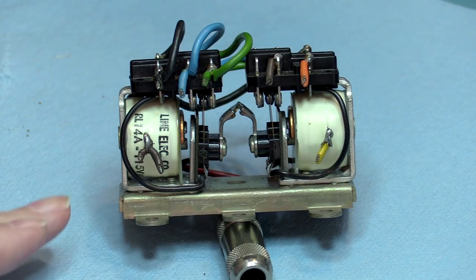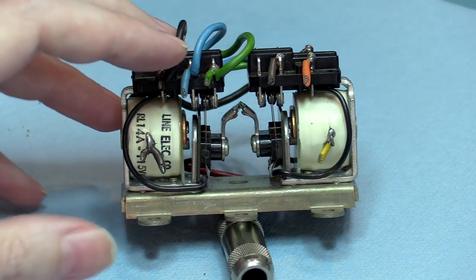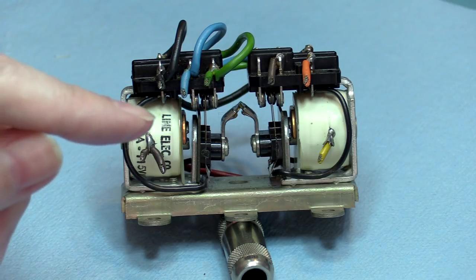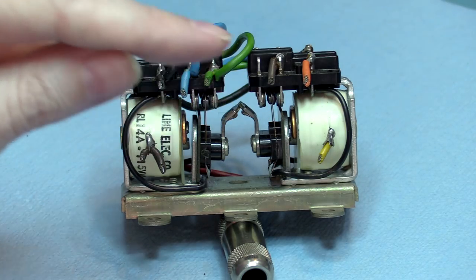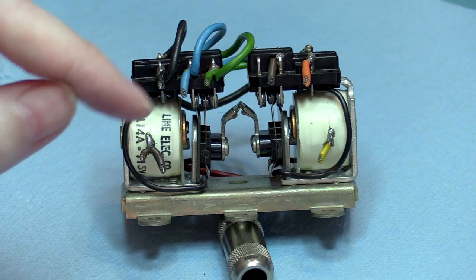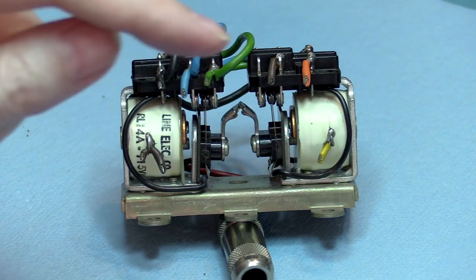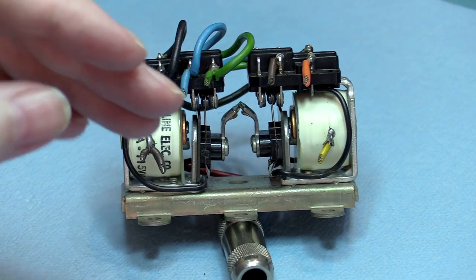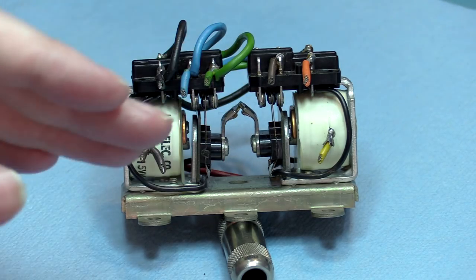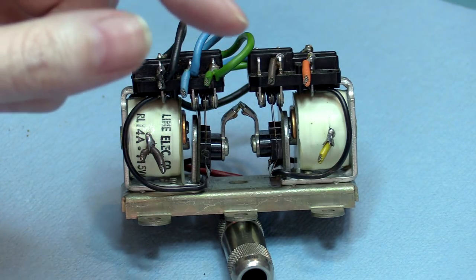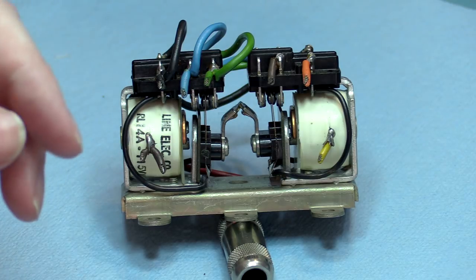So with a traditional relay-based flip-flop, you would have one of the poles of both of the relays used to hold current on one of the solenoids to keep the two relay flip-flop engaged one way or the other, and then use the other spare contacts in the relay for doing the switching, whatever you want to switch.